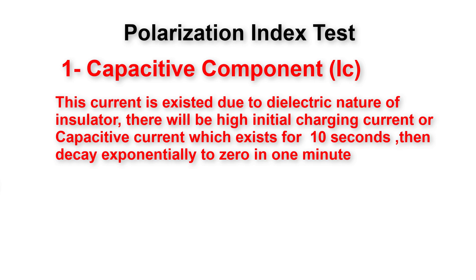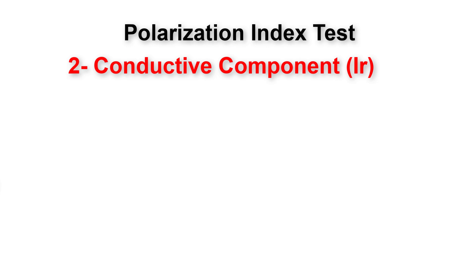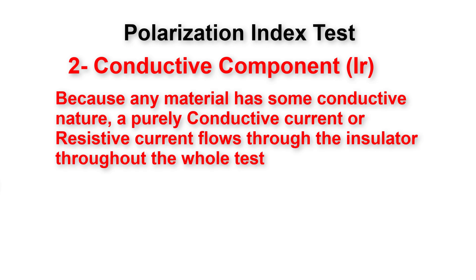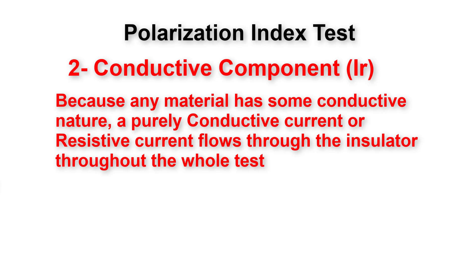Due to the insulator's dielectric nature, there is an initial high charging current, or capacitive current, which exists for about 10 seconds and decays exponentially to zero within 60 seconds, or one minute. Additionally, a purely conductive current flows through the insulator throughout the whole test, because any material has some conductive nature.